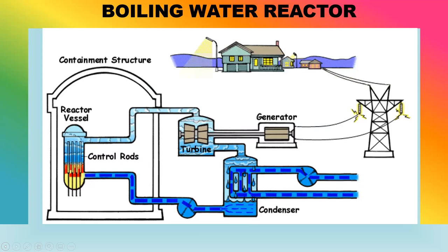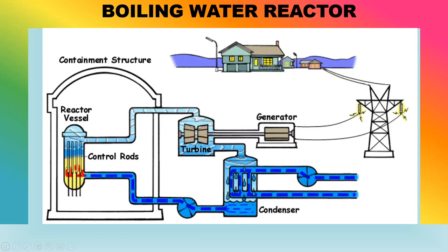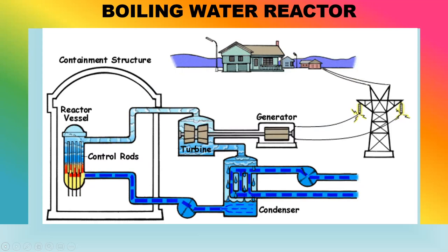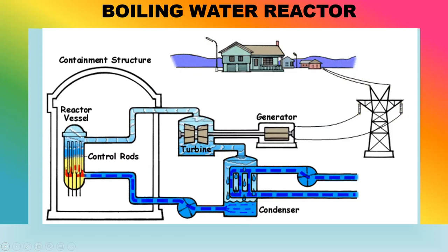But the water going through the reactor will become slightly radioactive. And then if you have any impurities in the water that's going back into the feed water, into the reactor, they can become radioactive. So your turbine and your steam pipes and everything in the steam plant might become slightly radioactive. So they have to deal with that problem in the design of the plant. And the steam turbine rooms are designed to contain any small amounts of radioactivity that might be there.